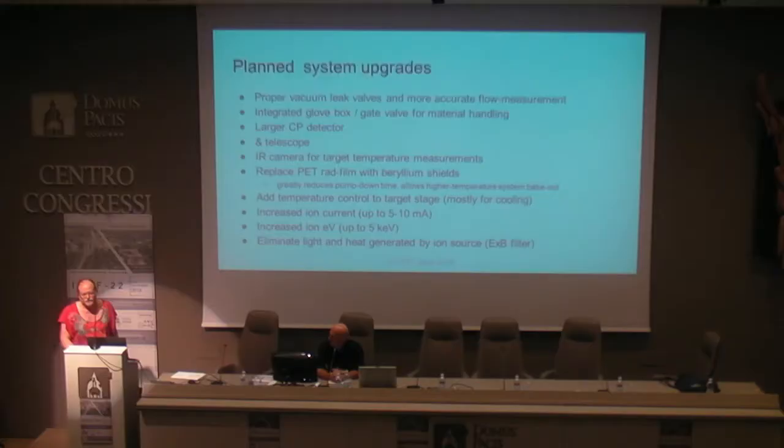I was going to see if you've thought to try to correlate the jumps and jags you're seeing in those parameters with something like acoustic or vibrational noise. I certainly would, and I will when I can do that. Getting an acoustic transducer, getting any transducer into an ultra-high vacuum system is a task. So everything we add has a significant cost.